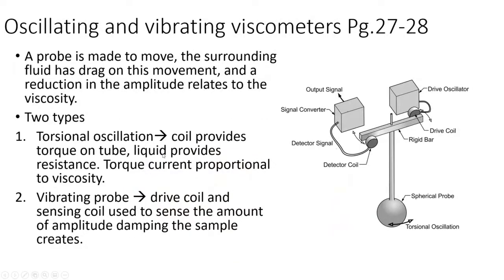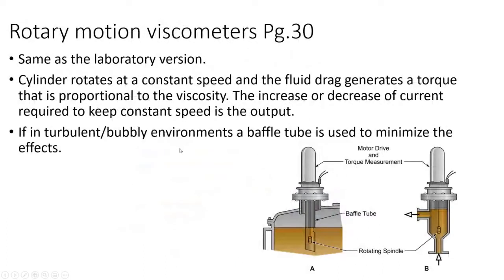The rotary motion viscometer is similar to the laboratory version: a cylinder or paddle rotates at constant speed, and the drag generated by the fluid creates a torque requirement proportional to viscosity. The increase or decrease in current required to keep constant speed is proportional to viscosity and is the output. If installed in turbulent or bubbly environments, a baffle tube is used to minimize effects — bubbles or turbulence cause a false 'thinness' reading.